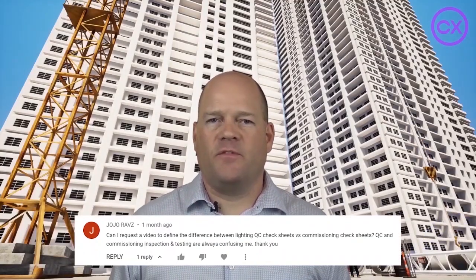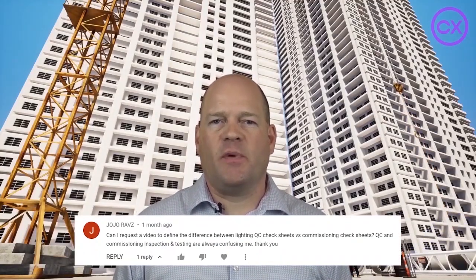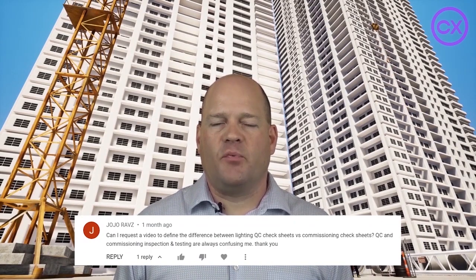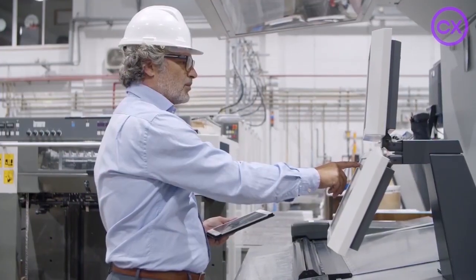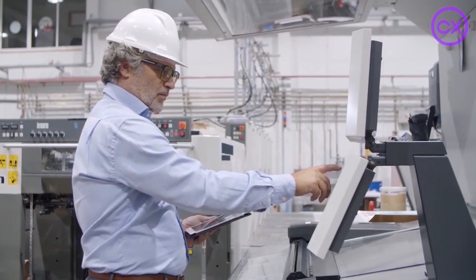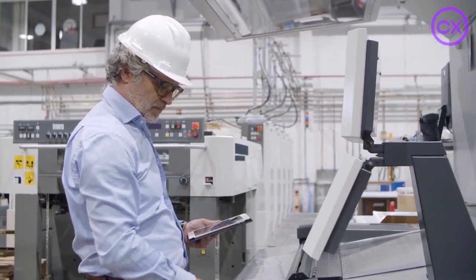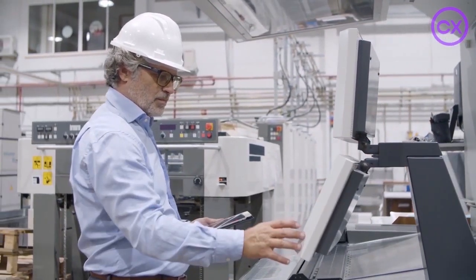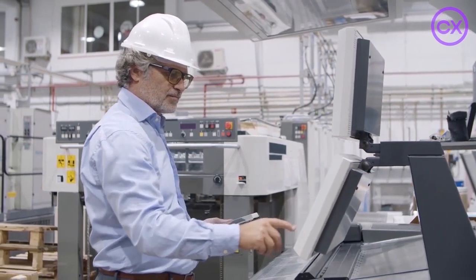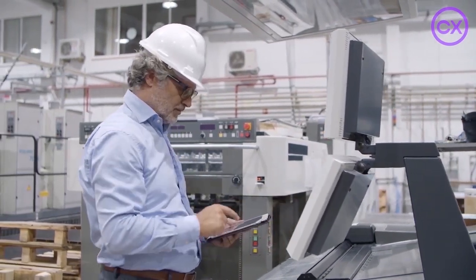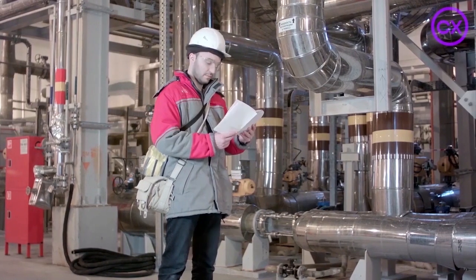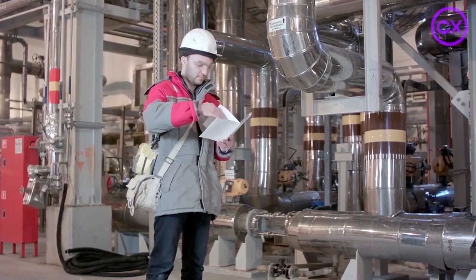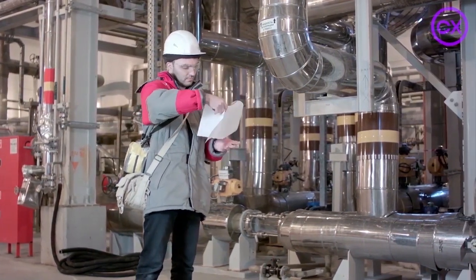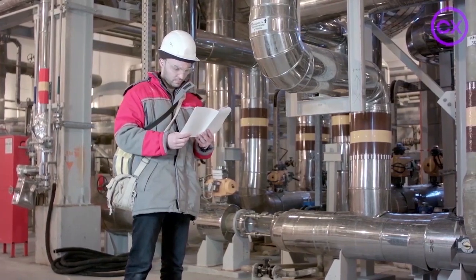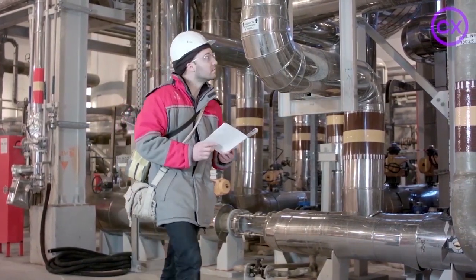This is the second part of Jojo's question, commissioning inspections. These are defined in pre-commissioning checklists. An example of a mechanical pre-commissioning checklist is a motor and a pump that requires startup for the first time. In this checklist, you'll have a bump test to confirm rotation, an uncoupled run to confirm no infant mortality issues, a coupled run to confirm current draw, and an initial run-in to confirm pressure and flow rates.